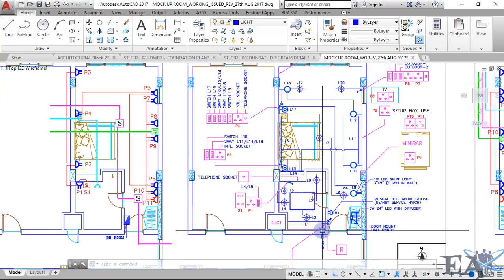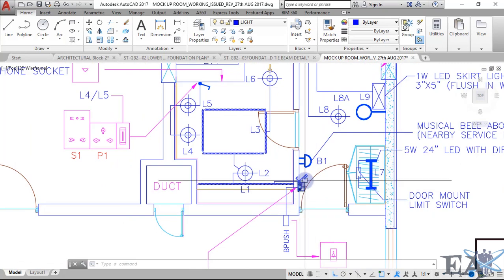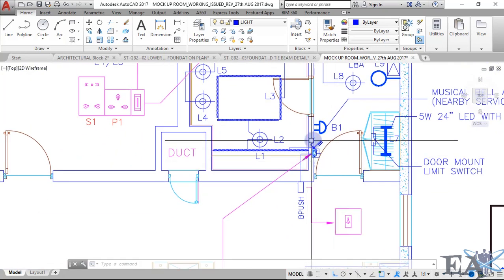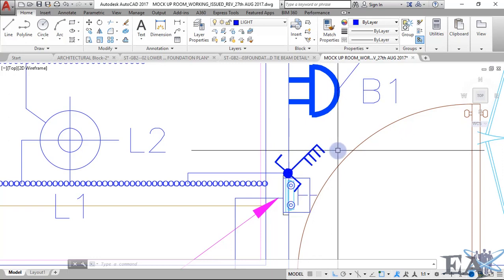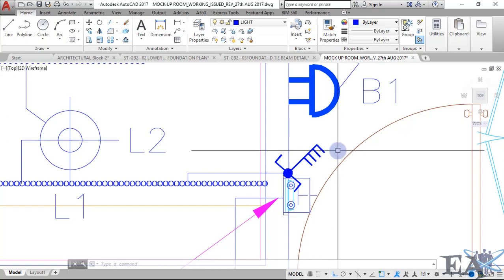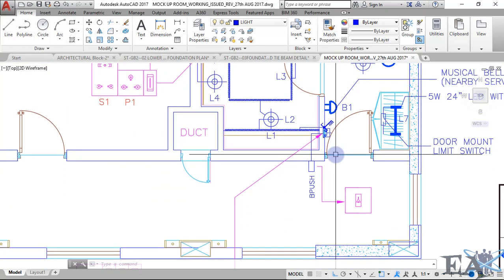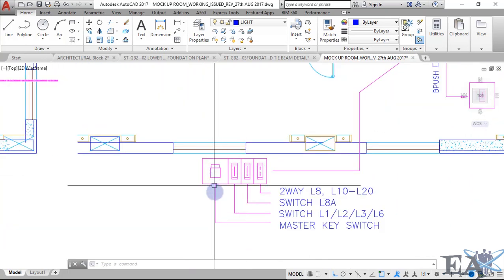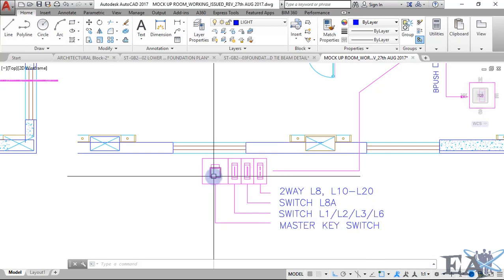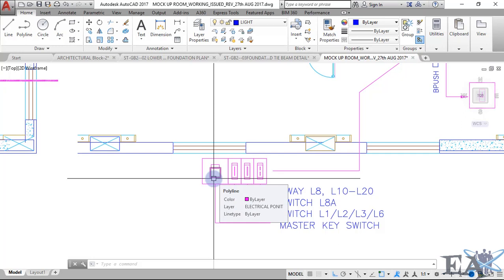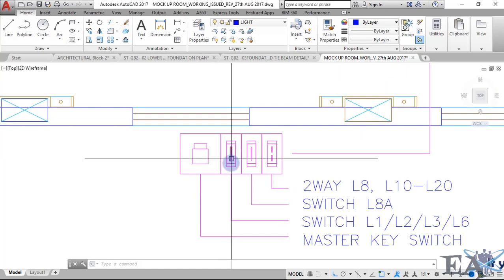Once you enter your room, you can see there is a switch shown with one, two, three, and four lines — that means it's a four-gang switch, so it will have four switches. The first one is a master key switch. If you've been into a hotel room, you'll be provided with a card similar to an ATM card, which you insert into the key switch. Once inserted, all your lights will glow and all your electrical power sockets will operate.